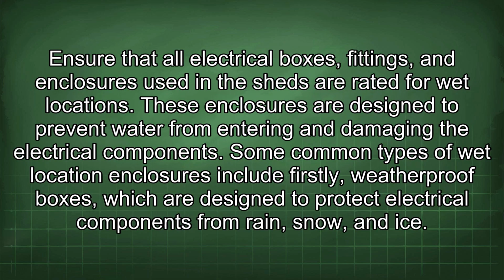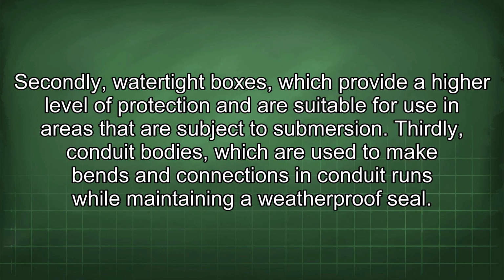Ensure that all electrical boxes, fittings, and enclosures used in the sheds are rated for wet locations. These enclosures are designed to prevent water from entering and damaging the electrical components. Some common types of wet location enclosures include, firstly, weatherproof boxes, which are designed to protect electrical components from rain, snow, and ice. Secondly, watertight boxes, which provide a higher level of protection and are suitable for use in areas that are subject to submersion. Thirdly, conduit bodies, which are used to make bends and connections in conduit runs while maintaining a weatherproof seal.